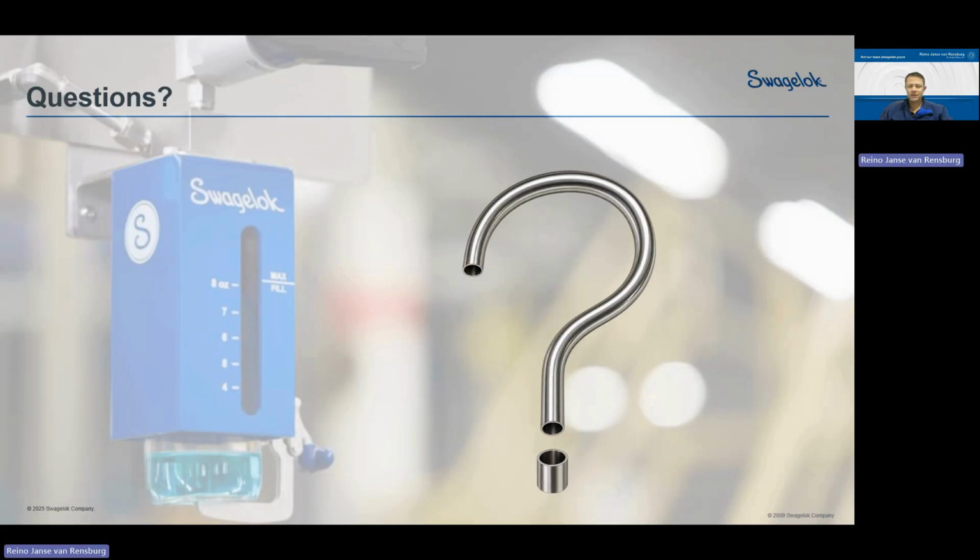Okay, yeah, so what I've seen is they change our flow rates to the analyzer, because they take off from the sample system into the bottle or whatever, and they adjust the flow rates because it takes too long to fill the bottle. And then they leave, and we have a massive flow rate which consumes probes and so on. So that is one thing. How would you solve that problem in this case?